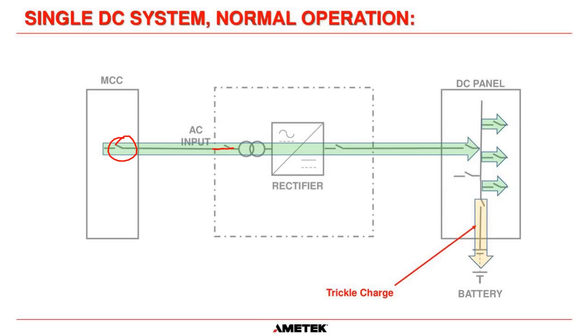And actually, at this point, I want to clarify that rectifier and charger are interchangeable terms in most circumstances. They mean the same thing. To rectify an AC signal is to change it from AC to DC, and a charger does exactly the same. The only thing with the term charger is it usually means there is going to be a battery connected to the system because you're going to charge the batteries. There are some circumstances where you will have a rectifier that does not have a battery connected, and therefore rectifier would be a better term, but they are interchangeable.